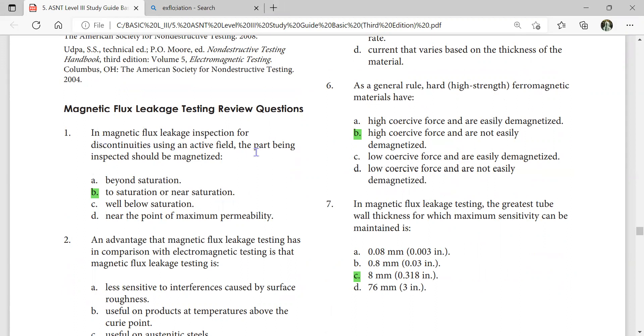In magnetic flux leakage inspection for discontinuities using an active field, the part being inspected should be magnetized to saturation or near saturation.